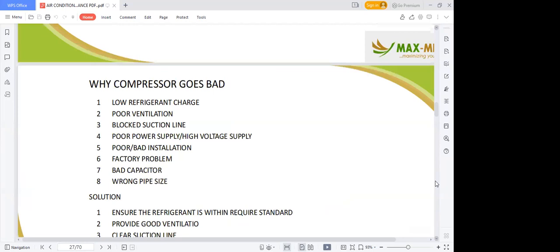Then, why does a compressor go bad? Low refrigerant charge. If your compressor does not have the required refrigerant, it can go bad, just like human beings not having enough blood within their system. Poor ventilation. You install your AC where there's no proper ventilation for the outdoor unit. There's a building I checked where the outdoor unit was installed about, let's say, 50 cm away from a wall. So most of the heat is hitting the wall and coming back to the AC. So most times the AC will shut down.